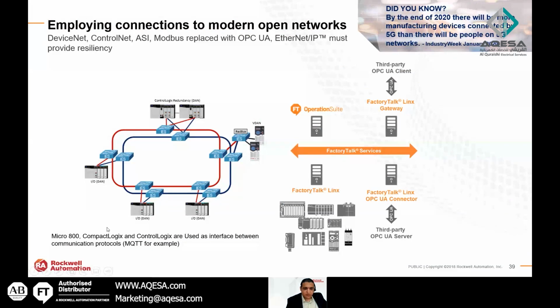Another new thing: the EN2T, the Flex 5000 adapter, the EN4TR, the EN2TP ControlLogix, these support PRP, Parallel Redundancy Protocol, where you have two redundant networks running separately. They can be star or ring topology, and you can communicate with ControlLogix or Flex 5000, Flex IOs, through EN2TP or EN4TR.